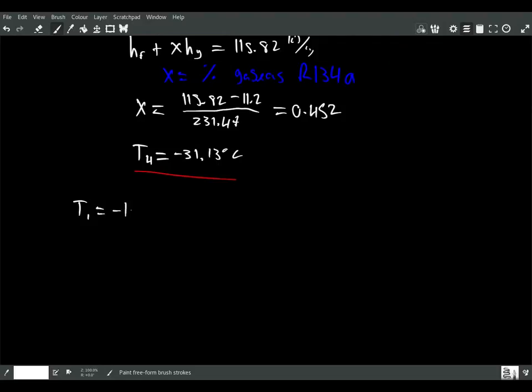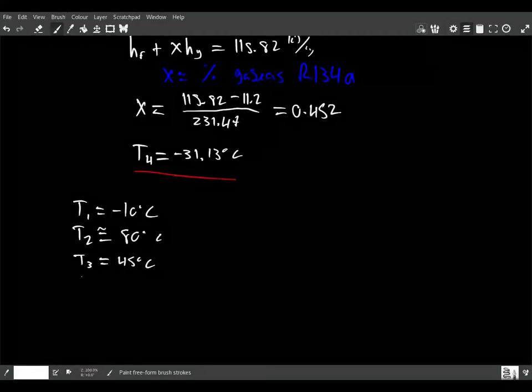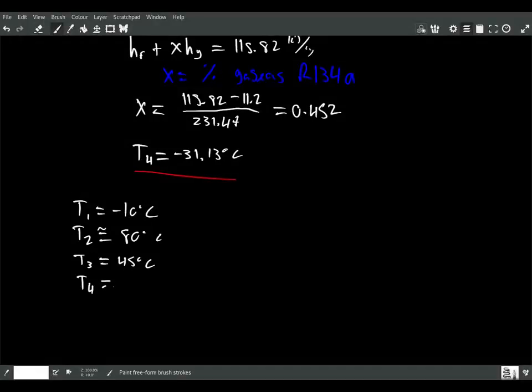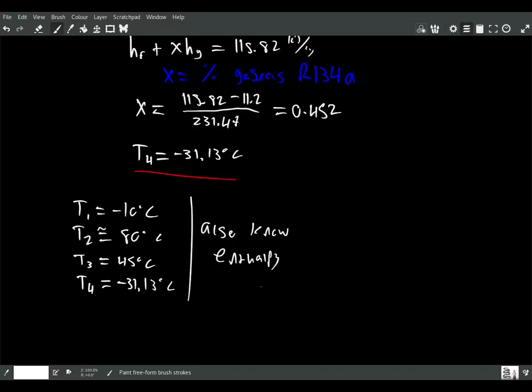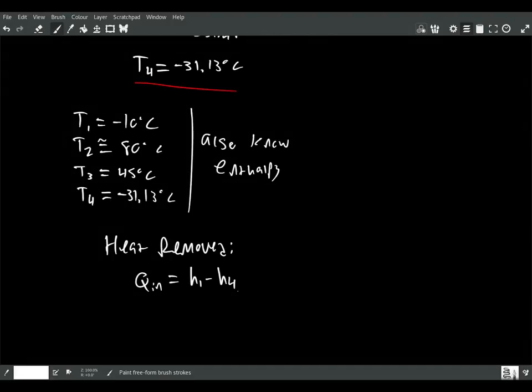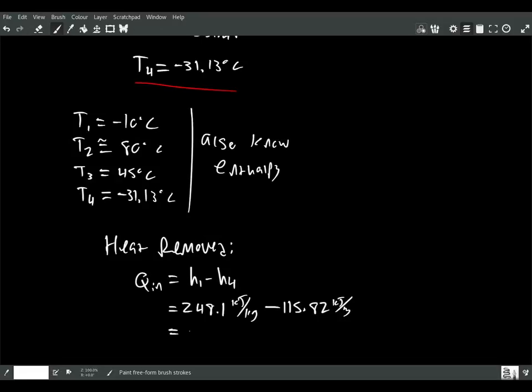To summarize the temperatures: T1 = −10°C, T2 ≈ 80°C, T3 = 45°C, and T4 = −31.13°C. Now we can determine the performance measures of the system. The heat being removed, Q-in, equals H1 − H4 = 248.1 − 115.82 = 132.28 kJ/kg.